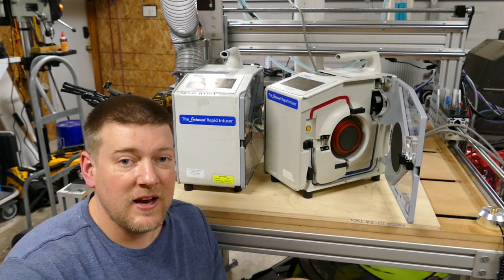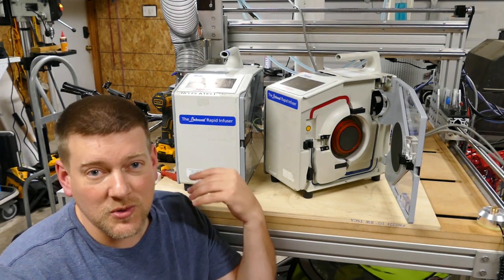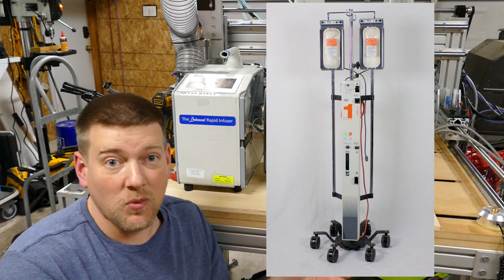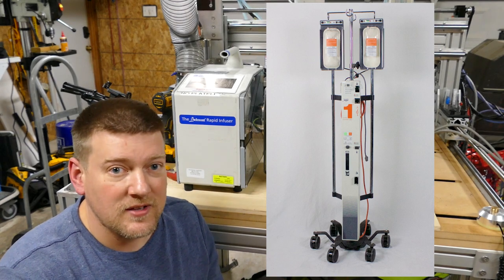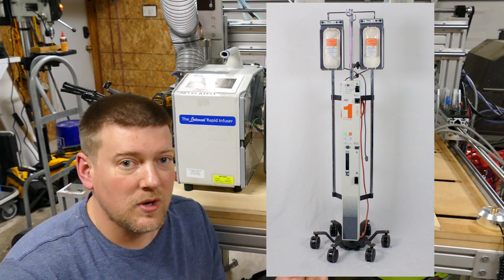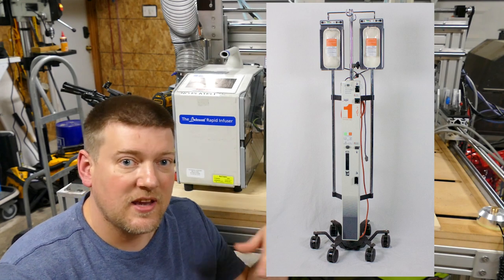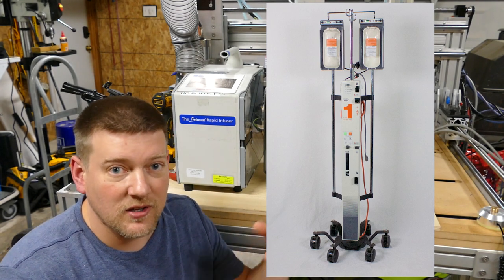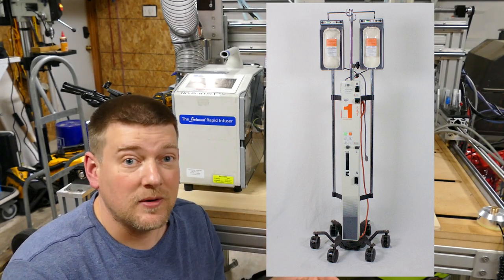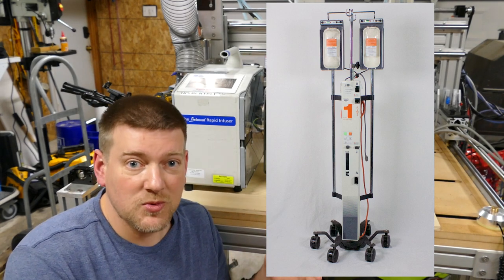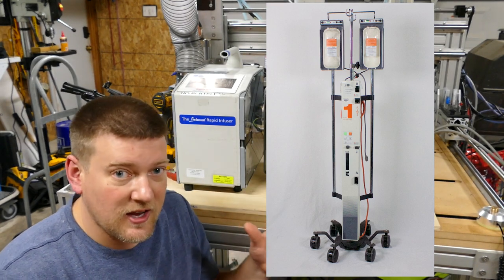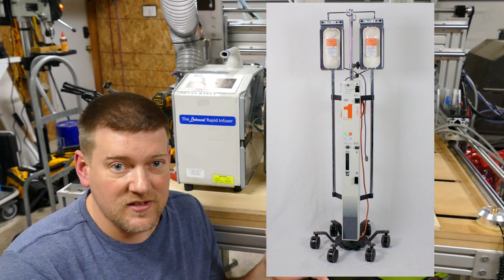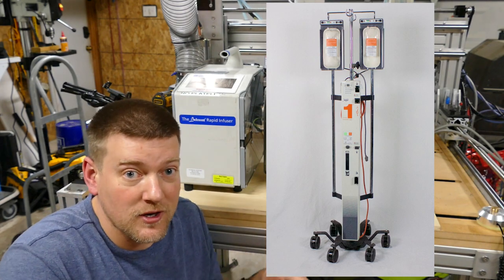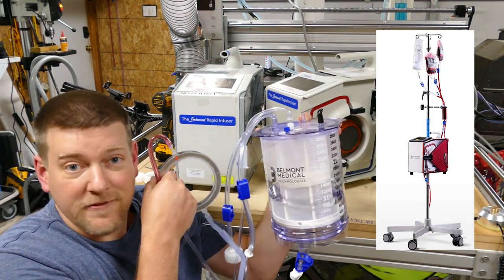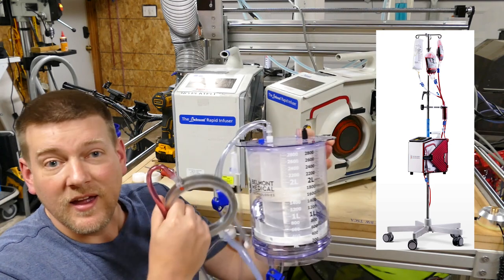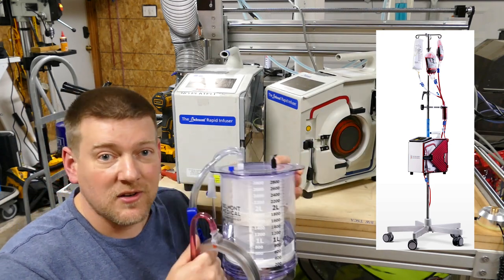There's some pretty big advantages to this system over the old school system, which would be your Level 1. The first is that the Level 1 system uses a fluid bath. And the fluid bath has to get up to temperature before it starts cycling at the selected temperature. This can create various problems with infection hazards because you constantly have stagnant water in a system on standby waiting for use. The FMS2000, however, has a completely dry, sterile set.